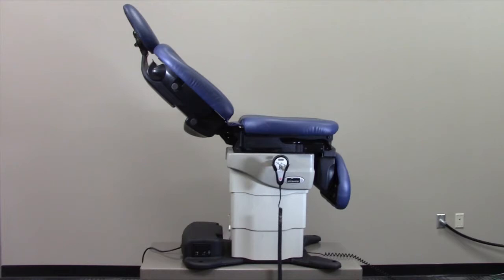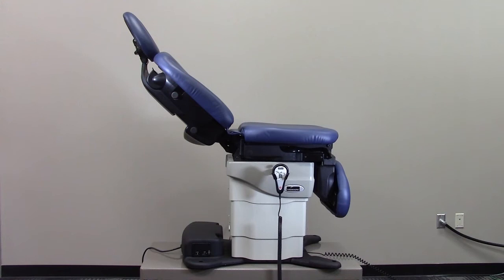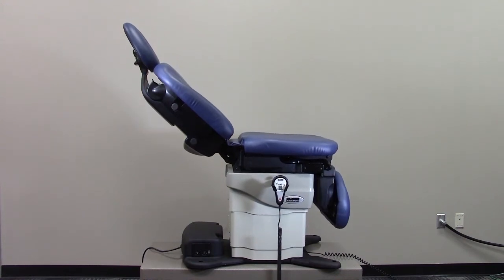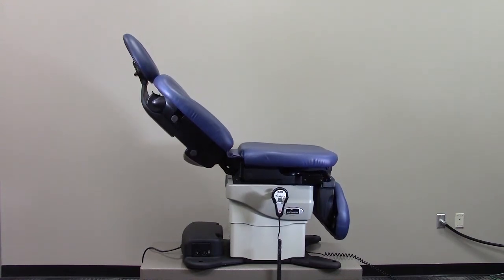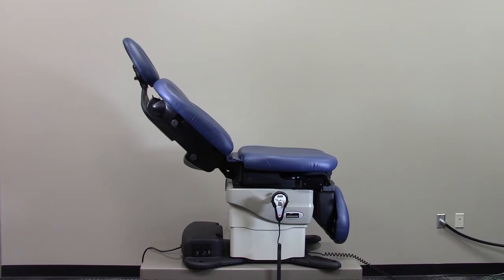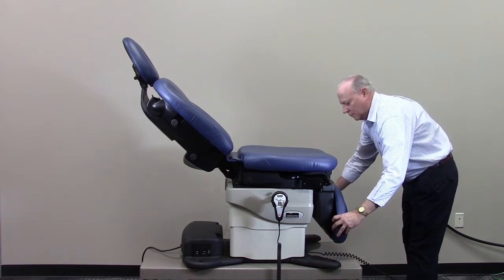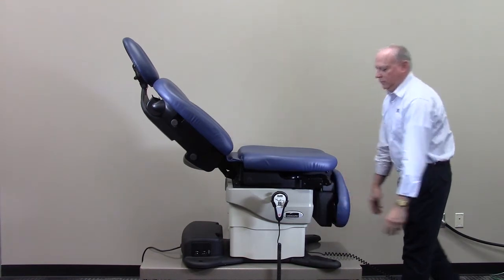In conjunction with the active sensing technology, the foot extension switch will stop downward movement of the base and tilt functions as well as the foot function if the foot extension is extended. If the active sensing technology is activated, it will sound a series of beeps and disable base down, tilt down, and foot down. Retracting the foot extension restores operation.